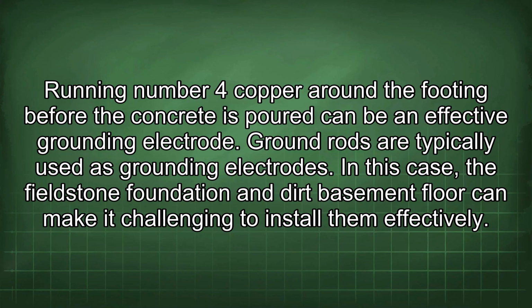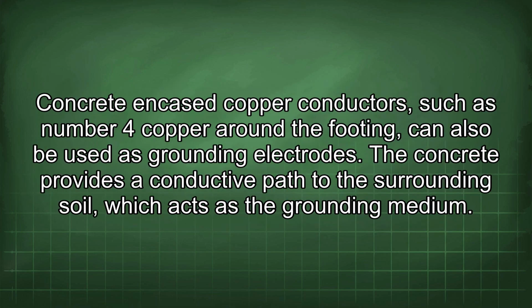Running number 4 copper around the footing before the concrete is poured can be an effective grounding electrode. Ground rods are typically used as grounding electrodes. In this case, the fieldstone foundation and basement floor can make it challenging to install them effectively. Concrete encased copper conductors, such as number 4 copper around the footing, can also be used as grounding electrodes.